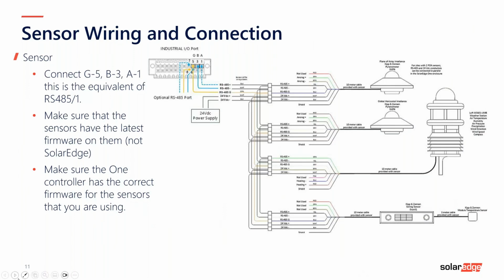They are, as you can see, wired in series, so they will be able to connect to each other on the roof, and then you have one cable coming back from the roof down to here. So all the cables basically are the same. There's no difference in the connections which you normally have from here. So on the CCG, you used to have all the different cables from the sensors wired back to the CCG, but you don't need to now. All you need to do is wire them to this. You've got a plus, a minus, a ground, and 24-volt plus and minus, and you just connect the sensor. So on the roof, you connect your sensor to this connection here, this connection then goes to the next one, and so on.